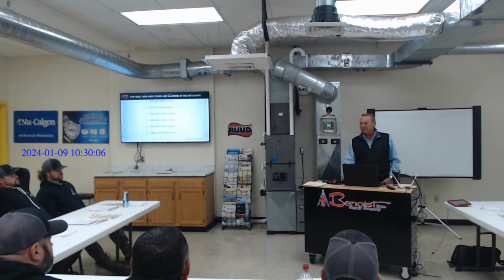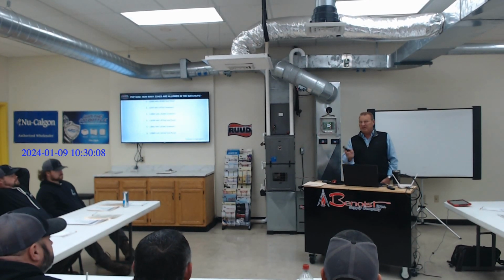We can lock it down a stage if it's a 2-stage, or especially in zoning. There's a little wiggle room, but there's not a bunch of wiggle room to fix that. Okay, well, you've oversized the furnace for the ductwork you've got, the customer got what they wanted, and now you've got a headache. That's the argument I just had with a guy the other day over St. Louis. Well, it's hard to sell a customer a downsize. Well, if the ductwork's not there, it's not there. You want the headache, fine, because you're going to have a headache with the new equipment.